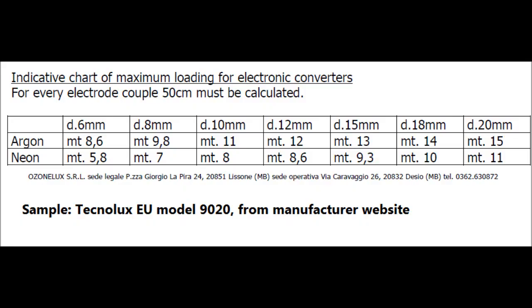The necessary output voltage is a function of the total tubing length on the sign, the tube diameters, and the amount of electrodes. You can get a footage chart from your transformer manufacturer or use tables of values for the volts per foot and per electrode pair.